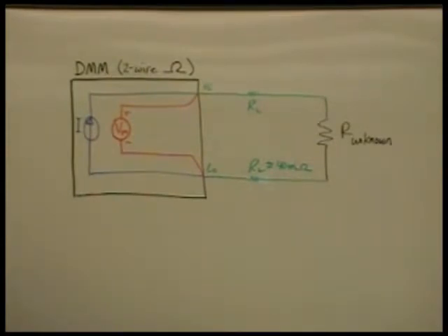On the whiteboard, I have a simple diagram of the DMM. The first thing I'd like to point out is that the DMM does not make resistance measurements directly, but we calculate those, and let me show you how that's done.